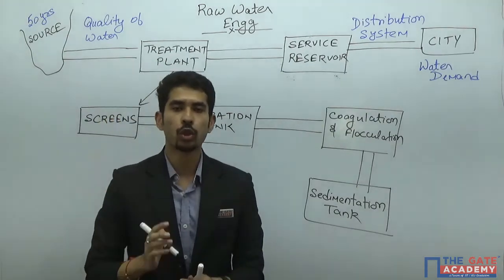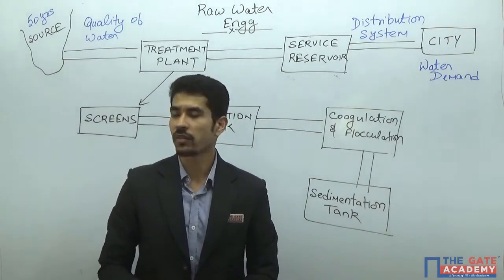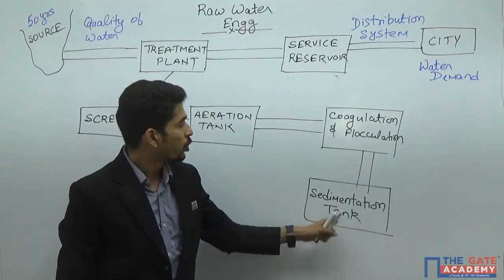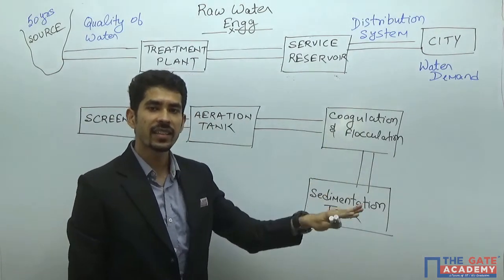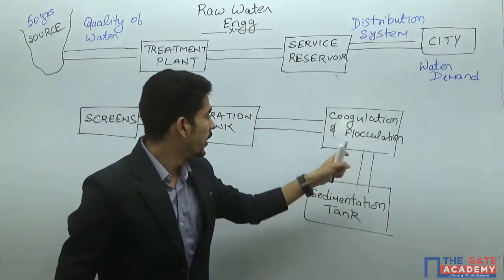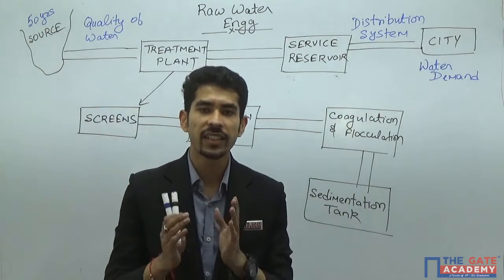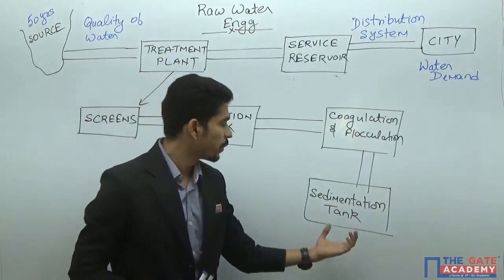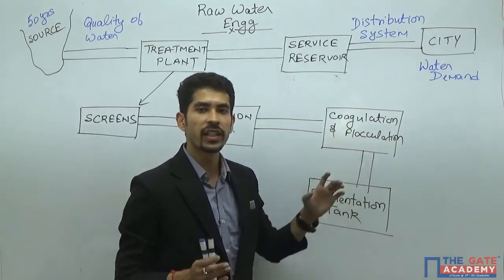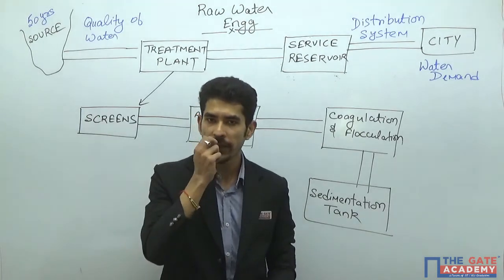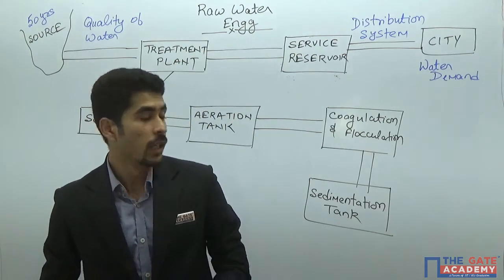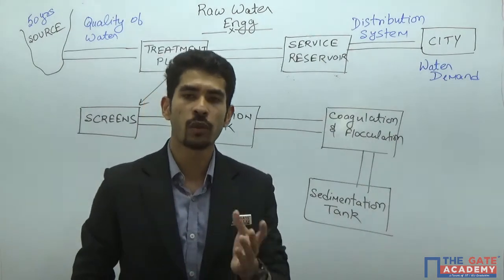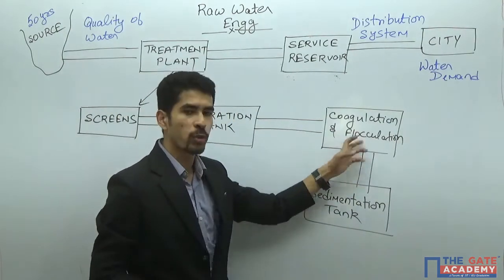Those suspended impurities which are not retained over screens are removed in the sedimentation tank. The coagulation and flocculation process increases the efficiency of your sedimentation tank. In this process, we are increasing the size of the suspended particles — if the size is larger, the settlement efficiency in sedimentation will be greater. If the normal efficiency of your sedimentation tank is around 60 percent, by using coagulation and flocculation before sedimentation, we can increase the removal efficiency of suspended solids to around 80 to 85 percent.